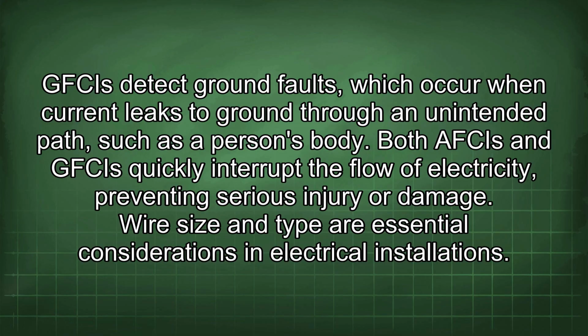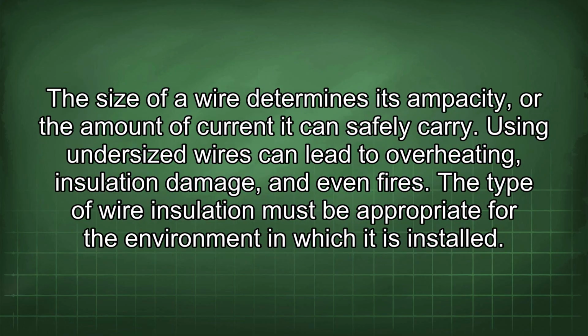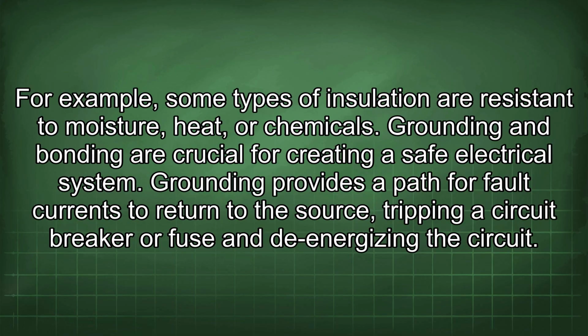Wire size and type are essential considerations in electrical installations. The size of a wire determines its ampacity, or the amount of current it can safely carry. Using undersized wires can lead to overheating, insulation damage, and even fires. The type of wire insulation must be appropriate for the environment in which it is installed. For example, some types of insulation are resistant to moisture, heat, or chemicals.